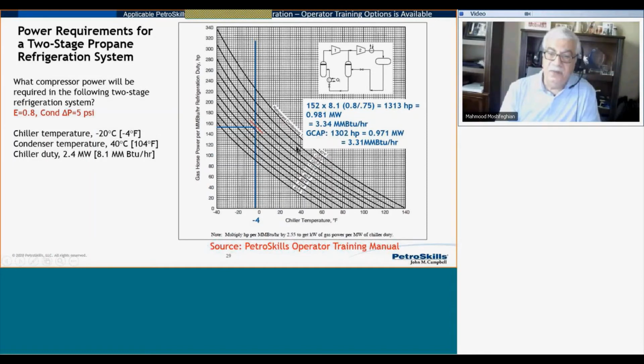Very surprisingly, very, very close to each other. So handy tool for quick calculation of power requirement. This is based on equal compression power, because I checked it with HYSYS to make sure how they generated the power requirement is the same. The power requirement for both stages are the same. And also, it was assumed the pressure drop is 5 psi in the condenser and discharge line to the compressor.